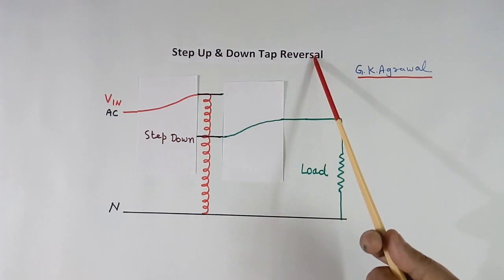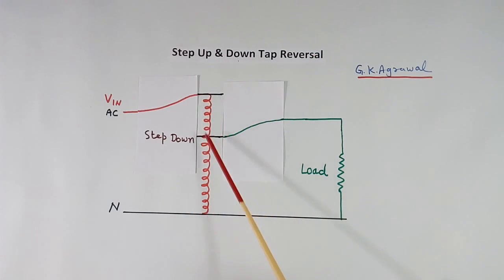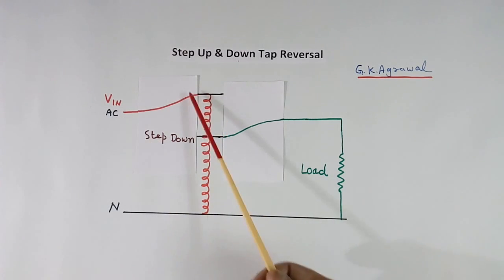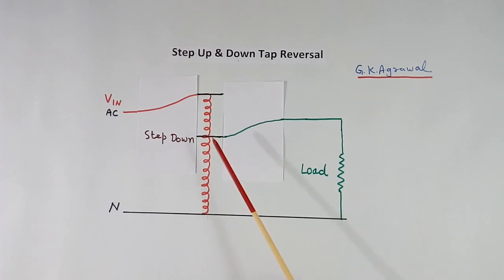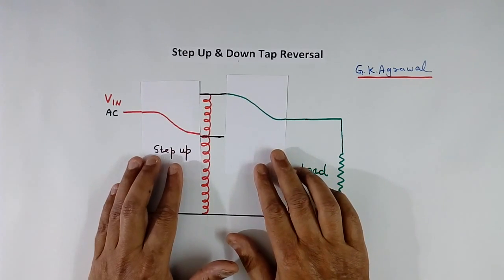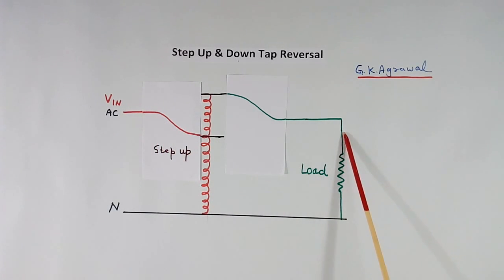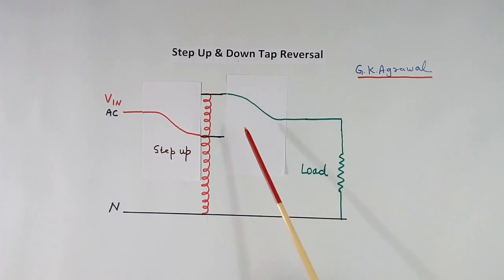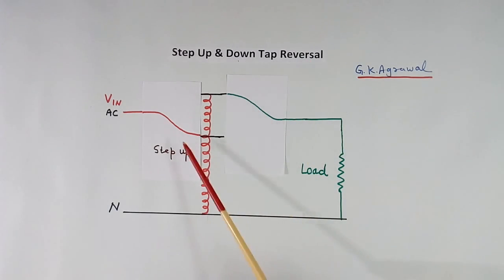Step up and down tap reversal. In this auto transformer there are two tappings. Higher turns are connected to input and lower turns connected to output, so turns at output are less — the voltage will be less, making it a step down configuration. Now the same transformer can be connected as a step up. Input is connected to the lower turns tap and the output load is connected to the higher turns tap, so it is a step up transformer — you will get more voltage. This change or reversal is done using switches, and by this method the cost of the transformer can be reduced.